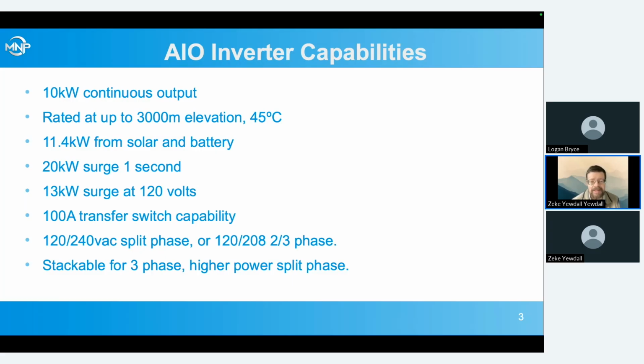And this is something that's a lot different than a lot of the all-in-ones. We can do a 13 kilowatt surge at 120 volts on just one leg. A lot of the all-in-ones, that's been a serious drawback, that they just can't handle imbalanced surge loads or heavy imbalanced loads at all. Like a 2 kilowatt air compressor killing a 6 kilowatt all-in-one just because it's on just one leg. So our inverter is one of the few that can actually do good surge capacity with imbalanced loads.